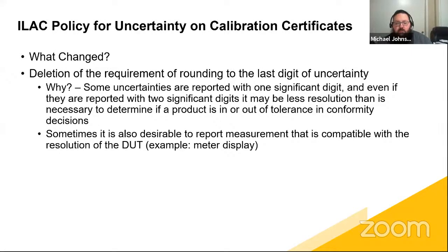So you stated that the contribution from repeatability can be 0, but according to GUM section F.2.2.1, even if it's 0, they would need to use that as a contribution. Do you have any comments? Yes, if it's 0, you add 0 as the contribution, so not out of line with what GUM is saying. And again, for the purpose of CMC, where you could have some variation, to kind of get out of that issue one of the previous questioners had. But yes, you would still put that in your uncertainty analysis as a 0, explaining why, but never, ever, ever for the actual measurement.